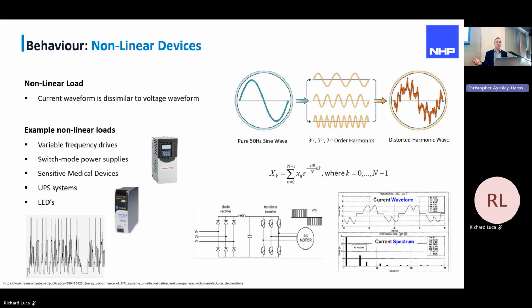But most of the loads these days, they're all non-linear, right? They're all driving efficiency, switch mode power supplies, a few examples there. Sensitive medical devices, UPSs, LEDs. So what happens when we connect these devices on the network? They introduce harmonic distortion, and they're odd multiples of the 50 hertz waveform. So when we superimpose that on the 50 hertz wave, we get a really distorted wave propagating throughout the network.